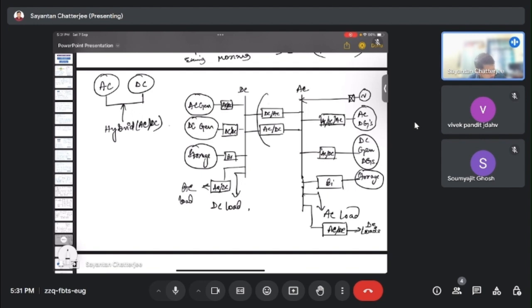So the main advantage of the AC/DC hybrid coupled microgrid is that whenever there is a mismatch, the grid is connected on the AC side, and when there are sudden mismatches between the AC and DC side grids, in those cases we can directly deliver power from the AC side to the DC side using the help of these interlinking converters.